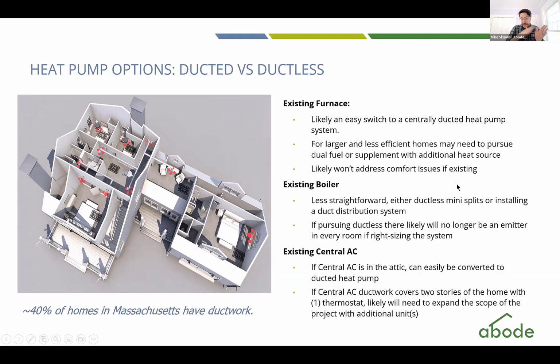Which path the homeowner should choose is likely going to mostly be dictated by what the heat load of the home is. So say, for example, the load of the home is 70,000 BTUs per hour. The biggest heat pump system for residential is around 50,000 BTUs per hour, so that person would likely need to put a heat pump on top of their fossil fuel fired system. But if the load of the home was 30,000 BTUs per hour, I think it's often goofy to be putting a heat pump on top of the furnace when a whole home heat pump system could be meeting 100% of the building's heat load.